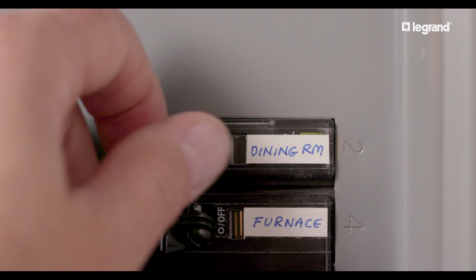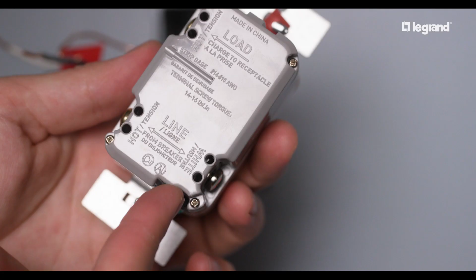To identify which is the hot wire in your wall, turn the circuit breaker back on. Without touching any exposed wires, test each wire with the voltage tester. The wire with no power is the load wire, and the wire with power is your hot. Now that you've determined which is which, go back and turn off your circuit breaker.